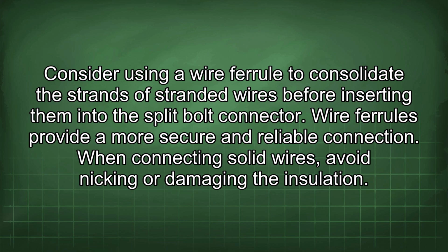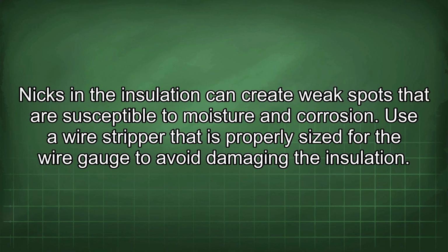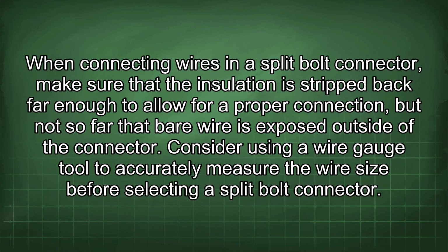When connecting solid wires, avoid nicking or damaging the insulation. Nicks in the insulation can create weak spots that are susceptible to moisture and corrosion. Use a wire stripper that is properly sized for the wire gauge to avoid damaging the insulation. When connecting wires in a split bolt connector, make sure that the insulation is stripped back far enough to allow for a proper connection, but not so far that bare wire is exposed outside of the connector.